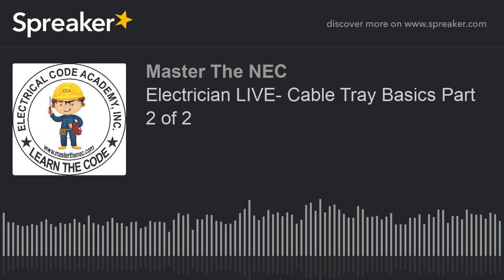And for those that aren't familiar with 310.18, for most applications, you wouldn't worry about it. But 310.18 is talking about ampacities of insulated conductors where it's not more than 3 current-carrying conductors in this application. If you look at it, this one deals with wiring installed in a 40 degree C ambient, whereas 310.16 is 30 degree C, and that's probably more of the applications that me and you are used to dealing with.